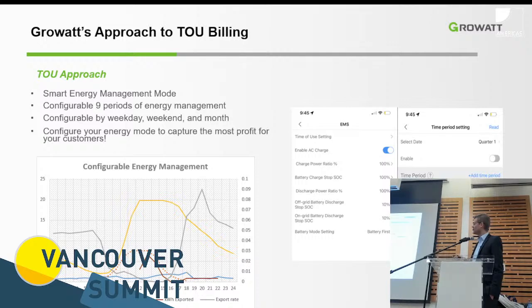The Growatt system has in the EMS, and that's part of that configuration guide I mentioned earlier, that you get asked what do you want to do and which of those features you actually want to implement with your customer. And you can specify how low you want to discharge on a daily basis, how much reserved capacity is there for grid backup, so that you're not discharging when the grid is still running, and then you're at 20%, and then a power outage happens. Then there's very little value to the customer because he's only living off the remaining 20% base, which will not last maybe over the entire night until the sun comes back up in the morning or the grid comes back, either or.